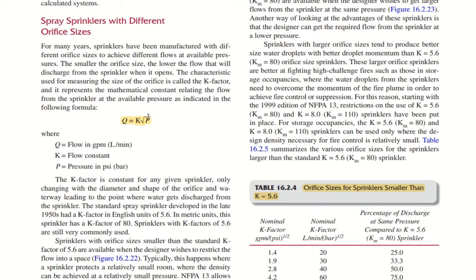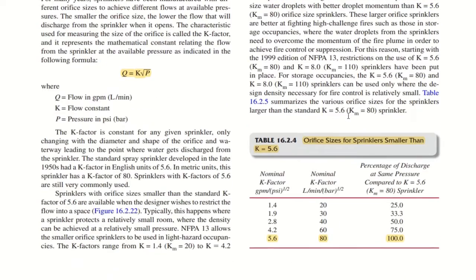This is an important formula, everyone I believe: Q equals K root P. Q represents flow in GPM, K represents the flow constant, P represents pressure in PSI. As we already discussed, minimum pressure will be 7 PSI. That has to be considered as per NFPA 13, and we can find out the flow in GPM for one sprinkler or n number of sprinklers with this formula. Okay, so this is also an important table. You need to go through the table thoroughly. You might get a question from this table as well in the examination.